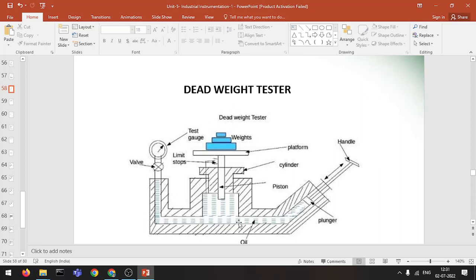So this dead weight tester apparatus consists of a chamber which is filled with oil free from impurities, and a piston cylinder combination is fitted above the chamber as shown in the diagram. The top portion of the piston is attached with the platform to carry the weights, and the pressure gauge to be tested is fitted at an appropriate place. The dead weight tester is basically a pressure producing and a pressure measuring device, and it is used to calibrate pressure gauges. The following procedure is adapted for calibrating the pressure gauge.